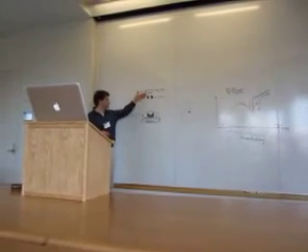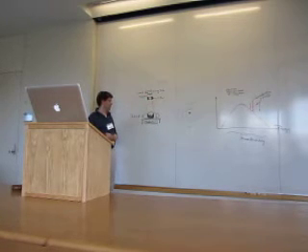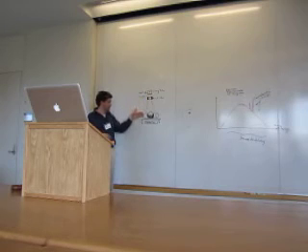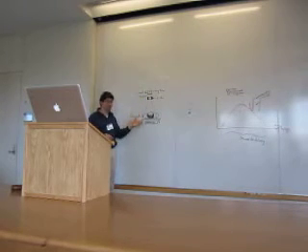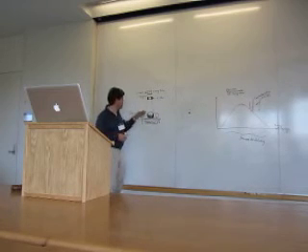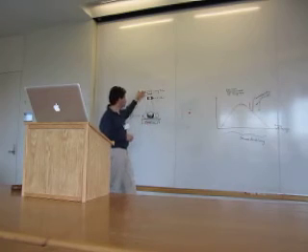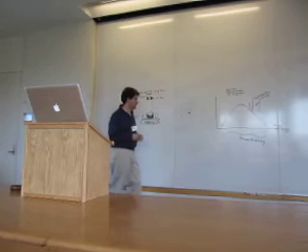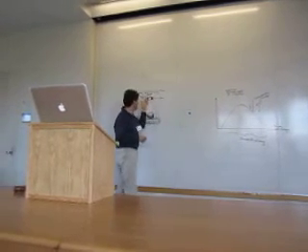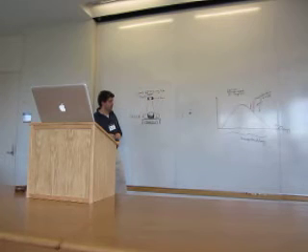So that X-ray beam is actually a kind of a broad fan of X-rays, and you have to do some filtering and collimating on it, and you shine it through your patient or object, and then you do a shadow image on the far side. Now, a little bit more detail on what those X-rays look like, specifically how much energy they get, and exactly what kind of interactions you see when the electrons slam into the tungsten.